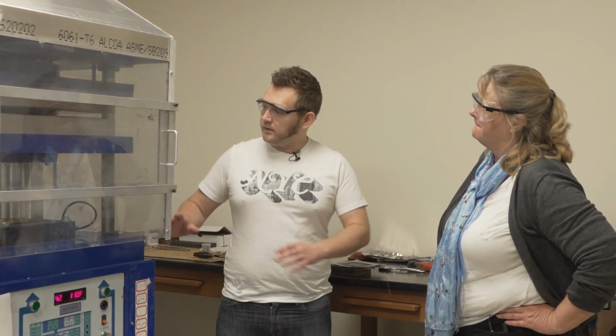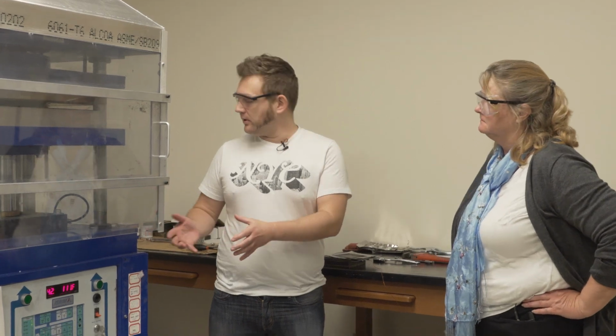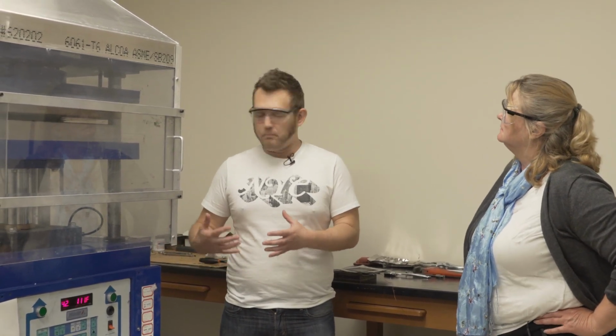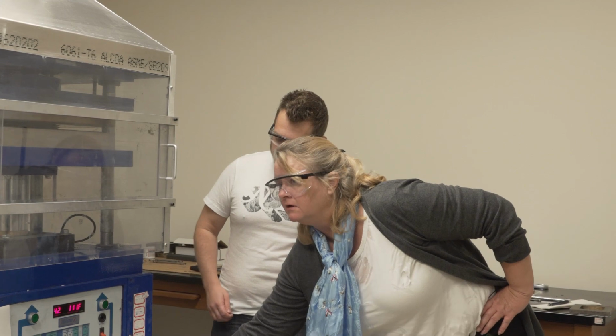And so the pressure inside here is generated with hydraulics — you have a pump down below where all of the hydraulic system is set up. When you start it, you can hear the pump going, and every once in a while you'll hear it kick in. If there's not a perfect seal, you'll get a little bit of leaking at times.